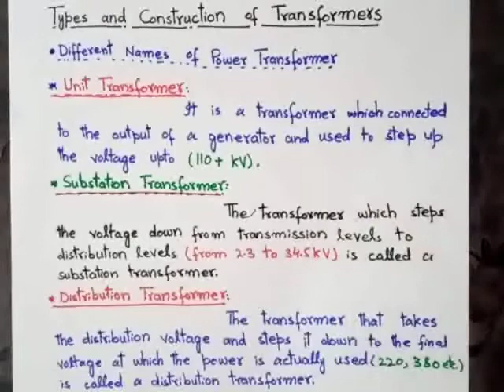The third type of the power transformer is the distribution transformer. The distribution transformer is the transformer that takes the distribution voltage and steps it down to the final voltage at which the power is actually used, that is 220 or 380 volt. It means the distribution transformer is also a step down transformer. In a distribution transformer, the step down voltages are 220 volt or 380 volt. If the voltages across the secondary side of the transformer are 220 volt or 380 volt, then this type of power transformer is called a distribution transformer.